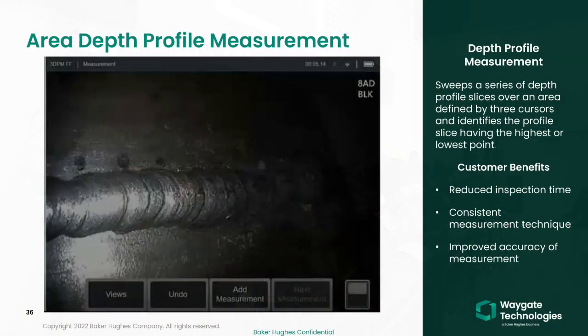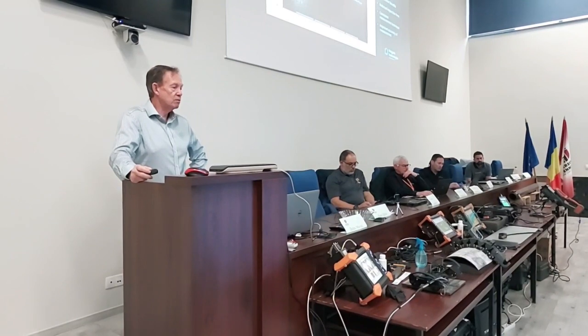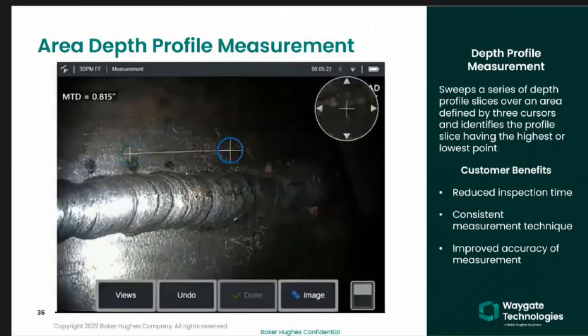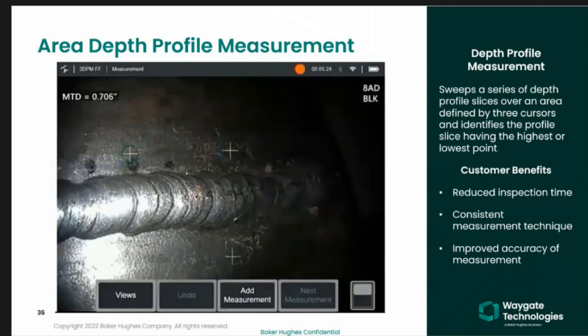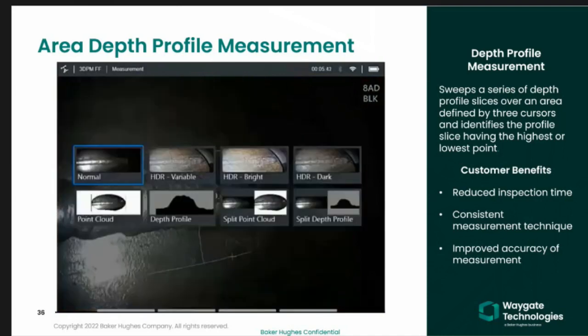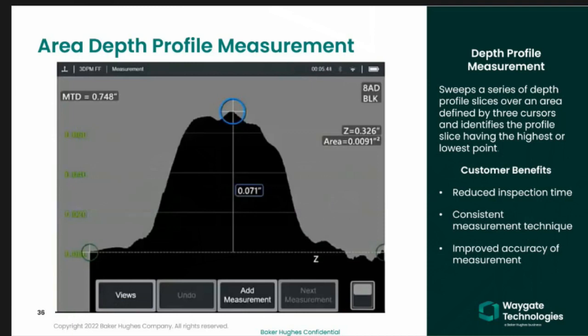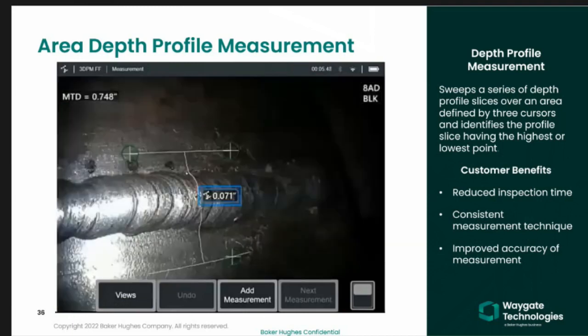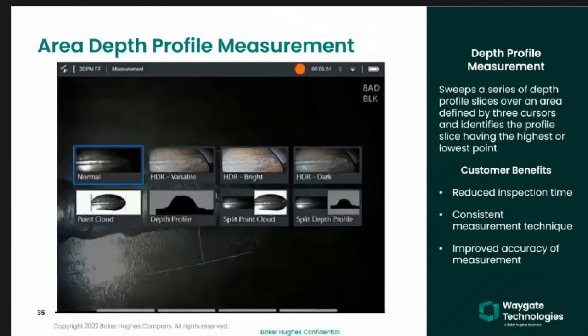This is a weld, so again we've got a different kind of measurement capability. Here we will do a depth measurement or area depth profile, scanning the actual route. The first 3 cursors it's putting in are lining up a datum - it needs a datum, that's what they call the green mask. The green mask suggests that between the 3 points it's plus or minus 1%. Then obviously you have more data, more features specifically regarding that.